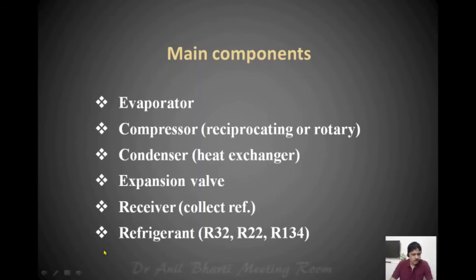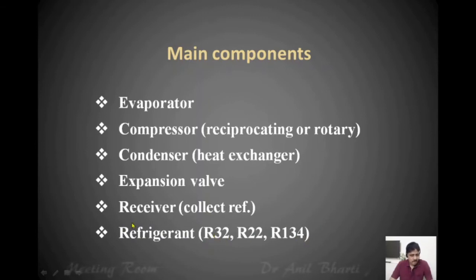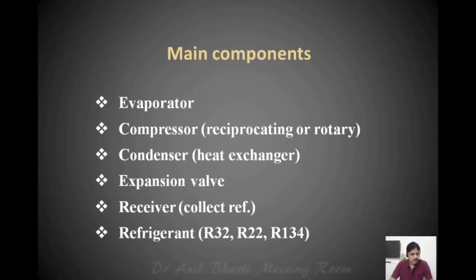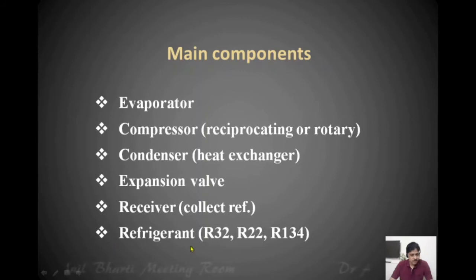The most important thing is the refrigerant. You may have heard of R32, R22, R134A — all these are various classes of refrigerants used in vapor compression systems. The refrigerant is so important that the design of the vapor compression system — the condenser coil thickness, diameter of the tube, evaporator tube dimensions, tube material, air-cooled or otherwise — all the design is based on the refrigerant we choose. So first of all we need to choose the refrigerant, and only then move on to the design stage of the vapor compression system.